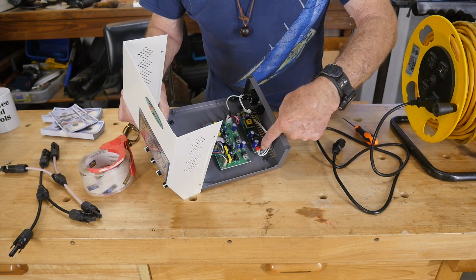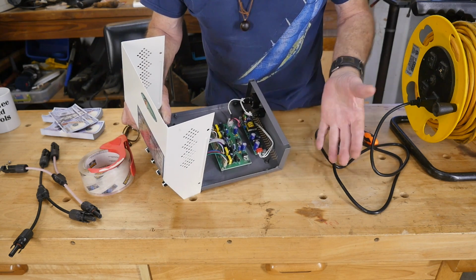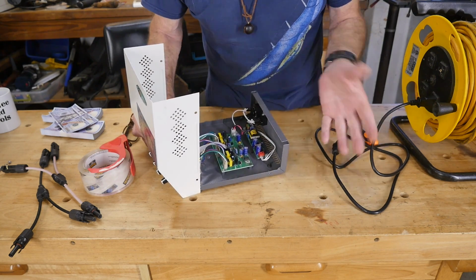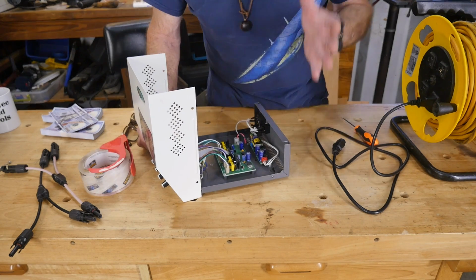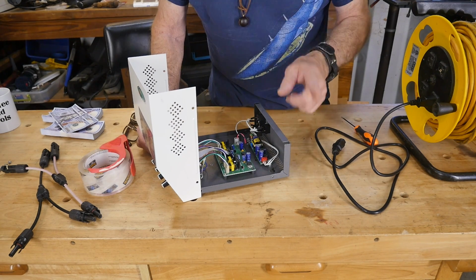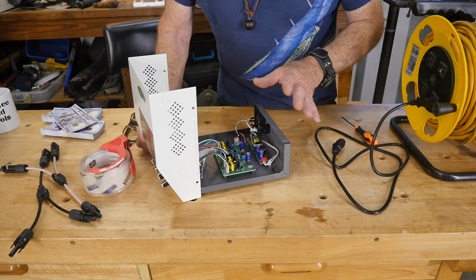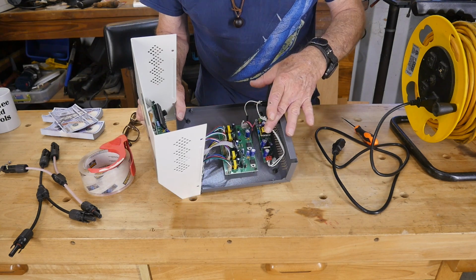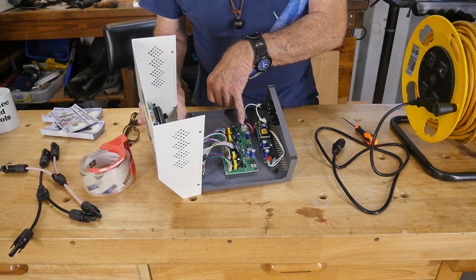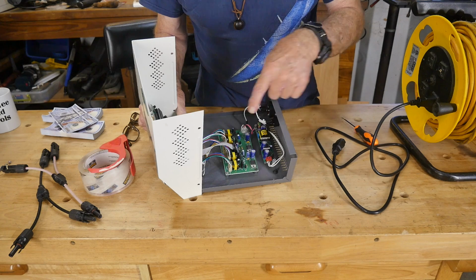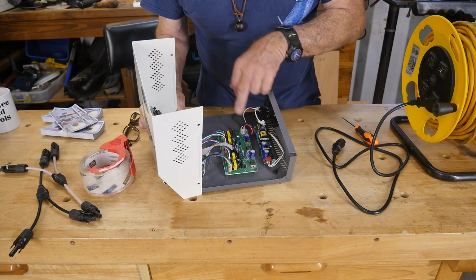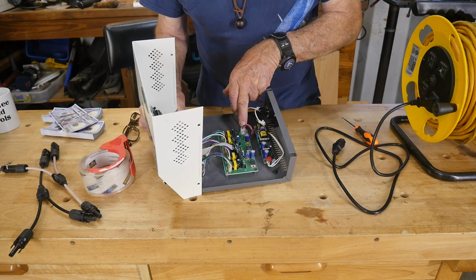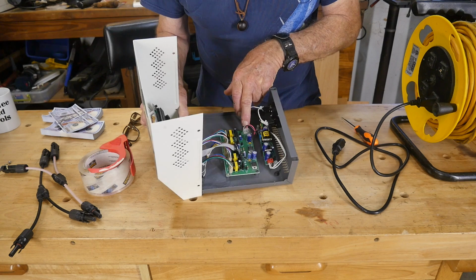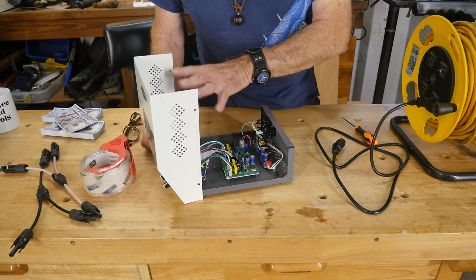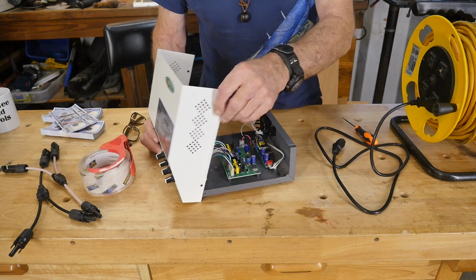What I did was I took a voltage reading off of here to indicate there's 110 volts. Yeah, okay, we have 110 volts on the meter. We're good to go. I'm going to bring something up later on about that anyways. In the meantime, the next thing I did was I ran off the neutral here and took power readings across here from the power supply coming in. And the voltage was fairly high, but the whole aspect of this is the machine doesn't work.